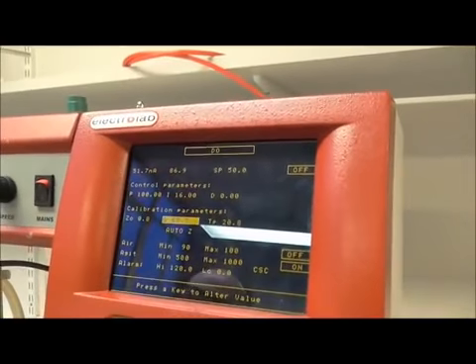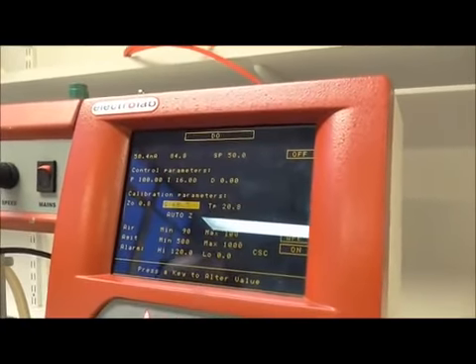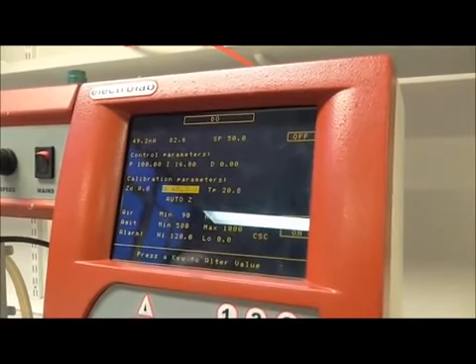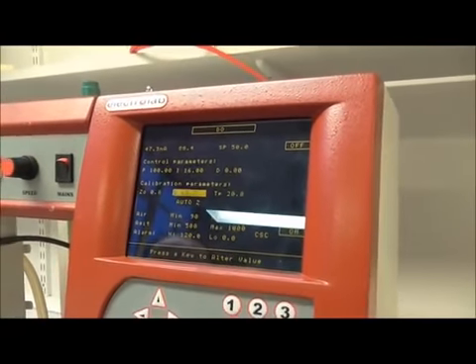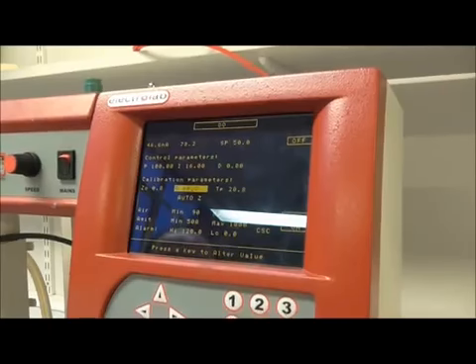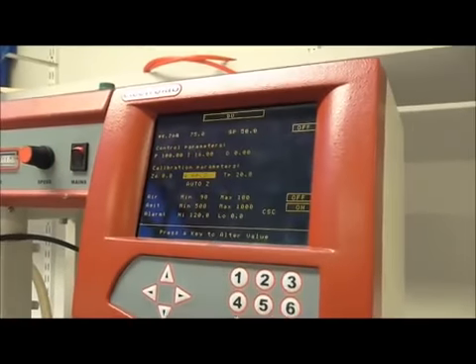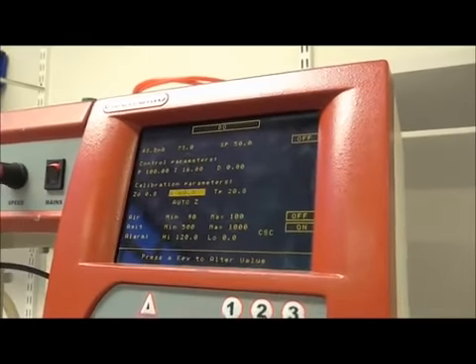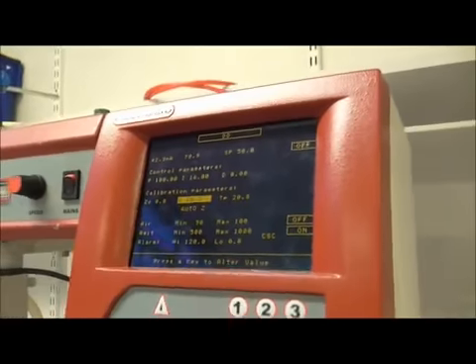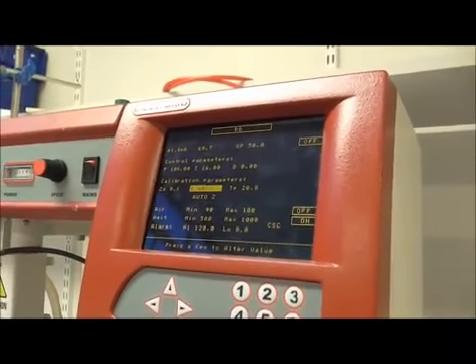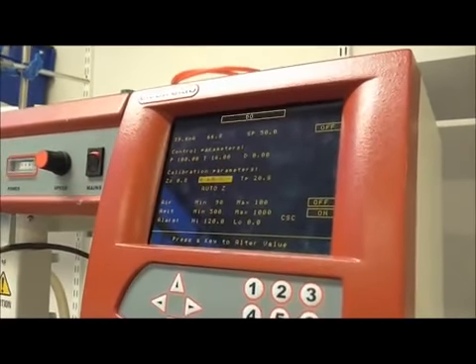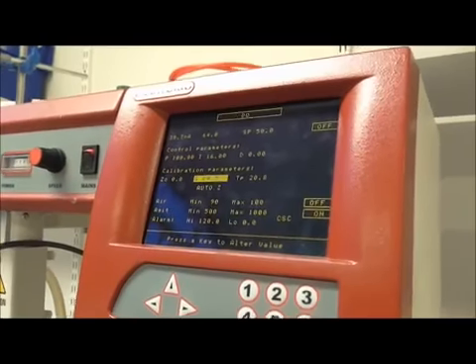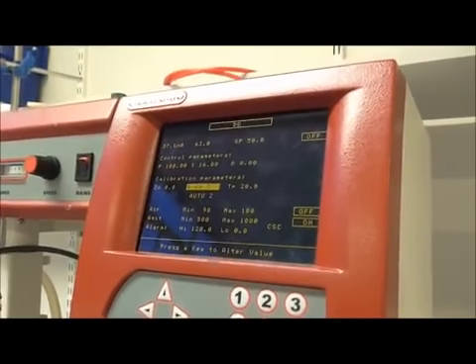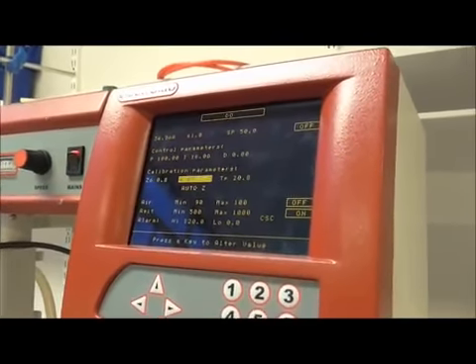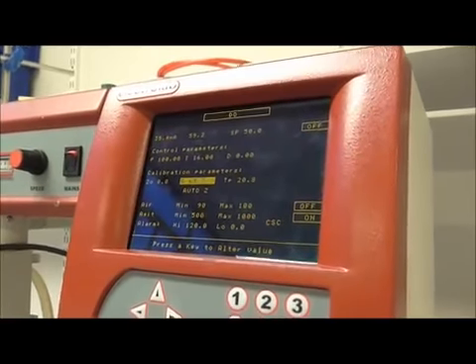Now we could do this in real time, but of course depending upon the age of the probe and various other factors, that will eventually sort of drop down to sort of near enough 0% dissolved oxygen. We can calibrate on the nitrogen, but we normally prefer to do it through the auto Z. This is just a check on the probe's performance. So you can see it's sort of falling away there.